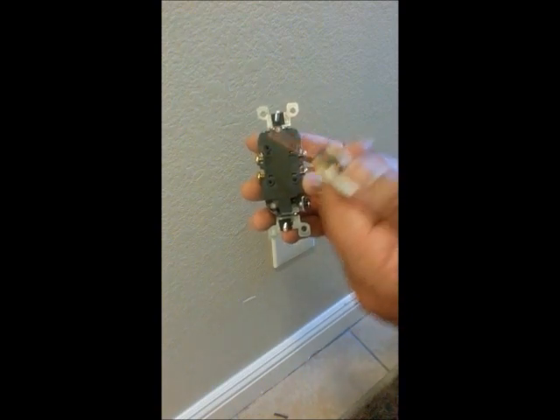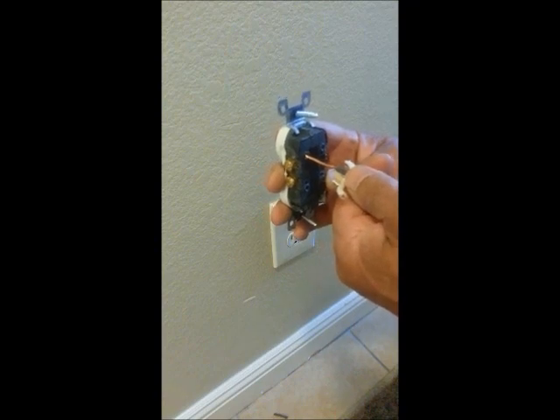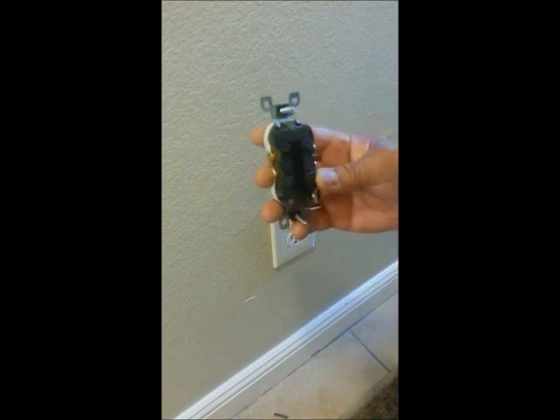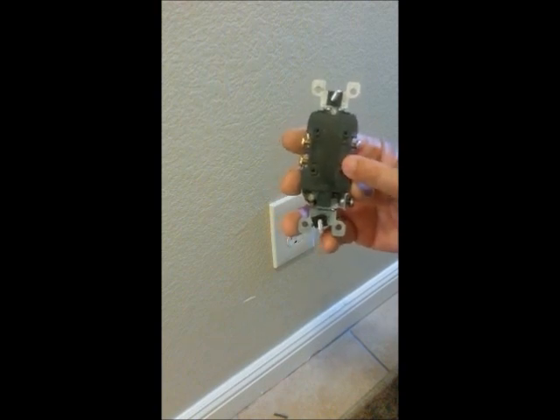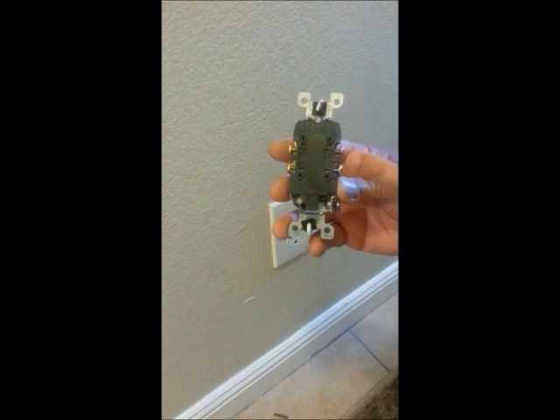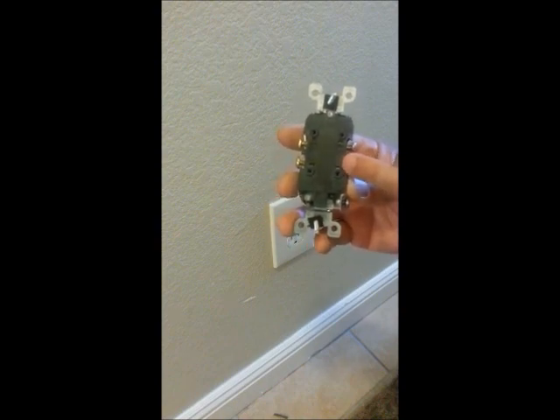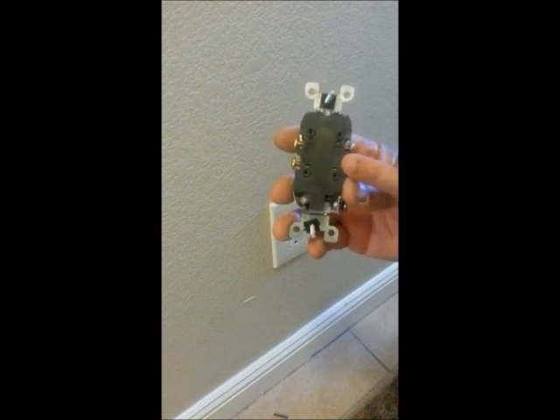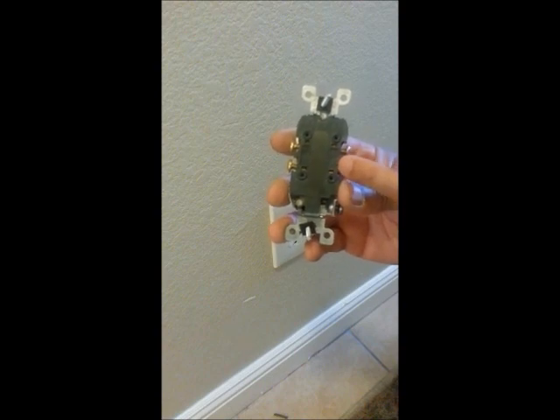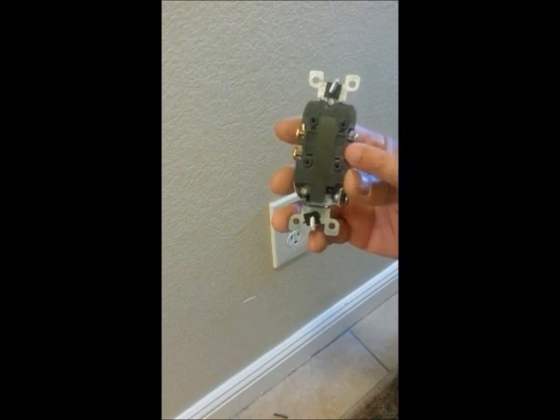This is 12 gauge wire. This will not go into a 15 amp outlet. They make these — these are commonly for your bedrooms, hallways, refrigerators, disposals, things like that that require more amperage. They'll have a 20 amp breaker, 12 gauge wire, and it'll also take a 20 amp outlet.